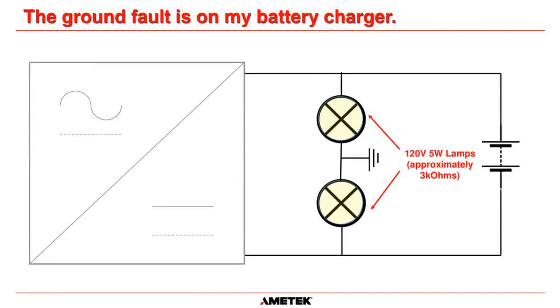Okay, so why, when I measure positive to ground and negative to ground, do I get 67.5 volts? Wow. That's because the charger manufacturer adds a circuit to detect ground faults, because we want to detect if there is a ground fault. And also remember this point. Having positive connect to ground doesn't give you an issue. You want to know that it's happened so you can clear the fault. It's only when the negative then connects to ground and has a separate fault that you would have a problem.